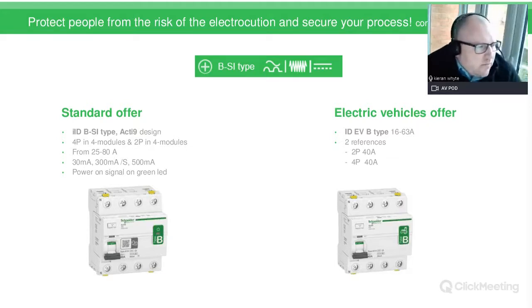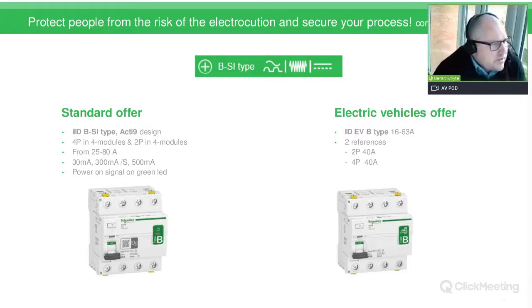So when we look at the B type, we have a standard offer in the B SI type in the Acti9 range, 4-pole and 4 modules, and there's also a 2-pole in 4 modules as well. Ratings from 25 to 80 amps, and then the 30 milliamp, the 300 milliamp time delay, and the 500 milliamp. It also has a power on signal indicator, a green LED. Specifically for the electric vehicle market, we do the 2-pole 40 amp and a 4-pole 40 amp.